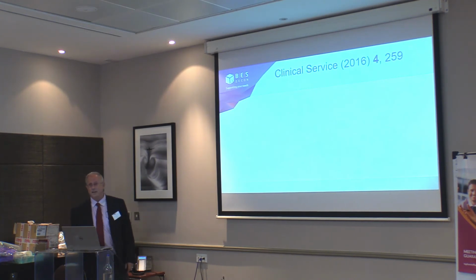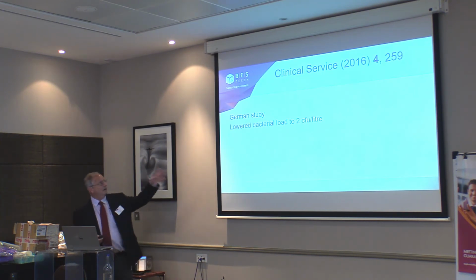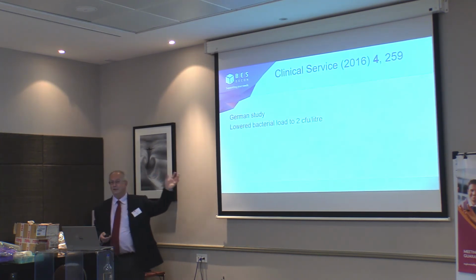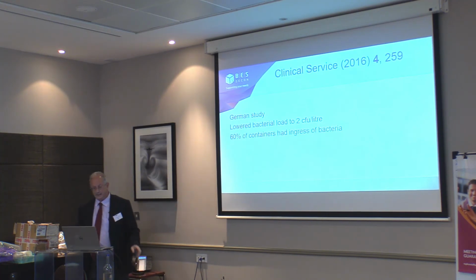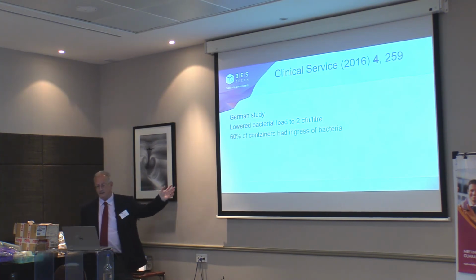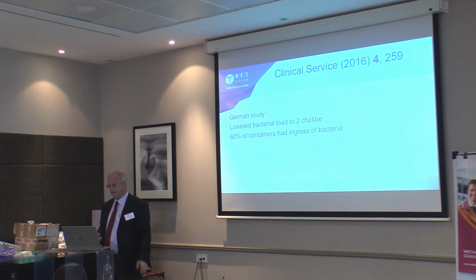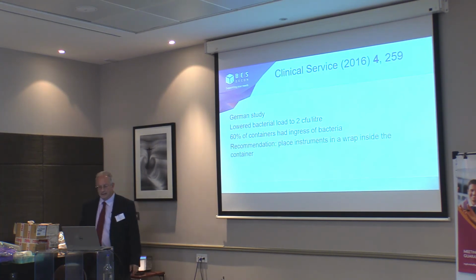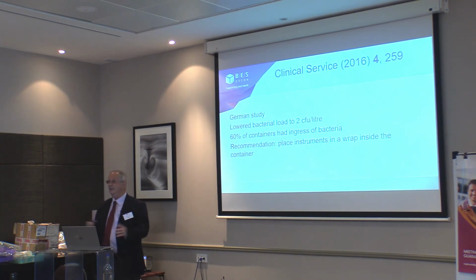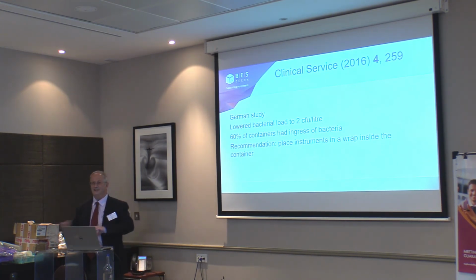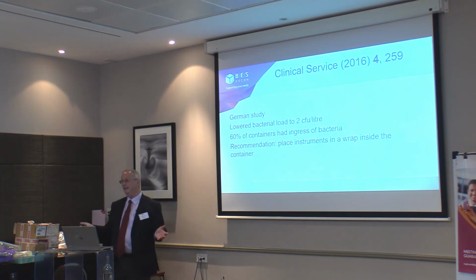The Germans had a look at this paper, and they did a study, and they used a lowered bacterial load of only 2 CFU. Before it was 250. They still found that 60% of containers had ingress of bacteria. Their recommendation is if you're going to use a container, use a wrap on the inside. Well, why use a wrap on the inside? Because you could have used the wrap around a tray anyway.